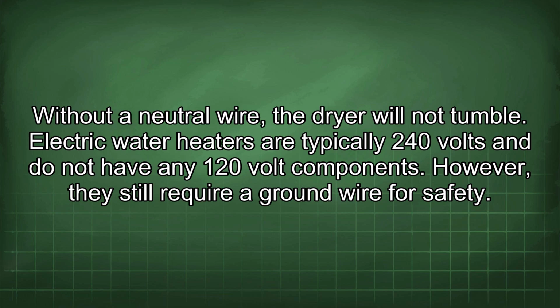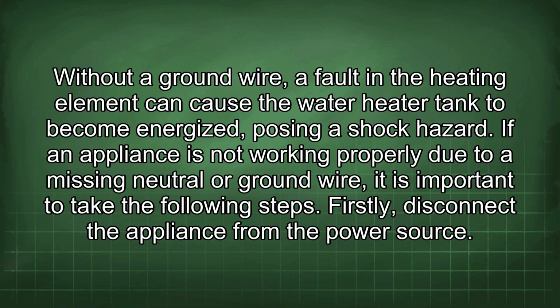Electric water heaters are typically 240 volts and do not have any 120-volt components. However, they still require a ground wire for safety. Without a ground wire, a fault in the heating element can cause the water heater tank to become energized, posing a shock hazard.